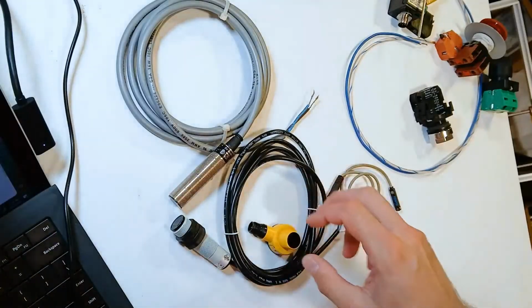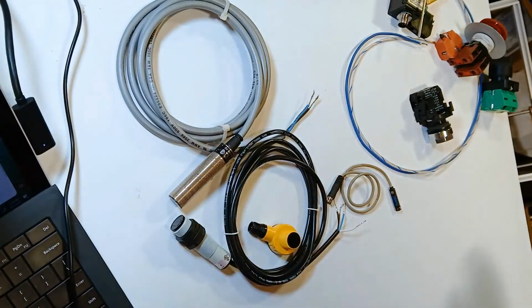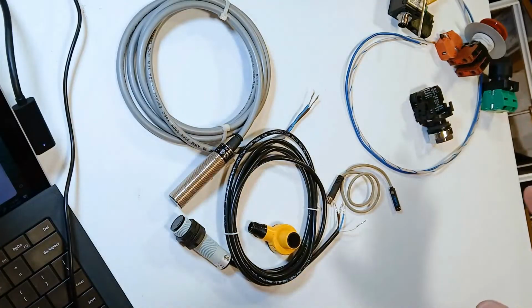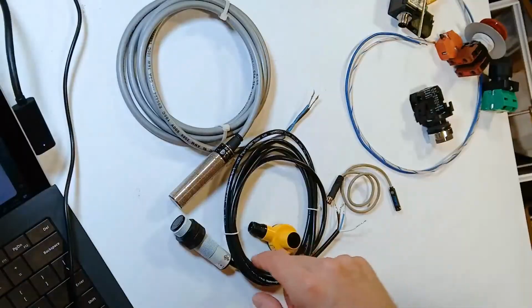Semiconductors with no moving parts last many times longer, and therefore the service life of a high-speed sensor is much longer. Are there a few cautions to these? Well, absolutely. With the mechanical switches, we could apply whatever voltage up to a maximum allowable, and everything below that was safe. With these three-wire sensors, they're going to need a certain amount of voltage to run the electronics inside, but if you provide too much voltage, you can destroy them.